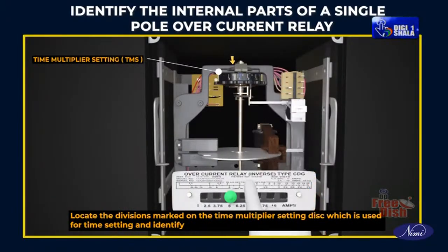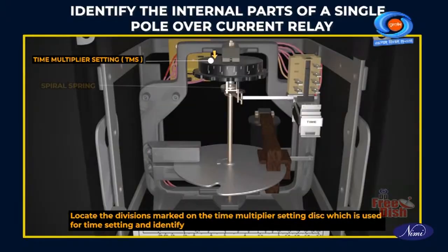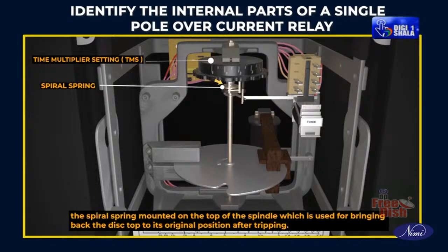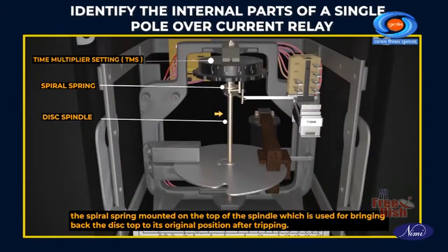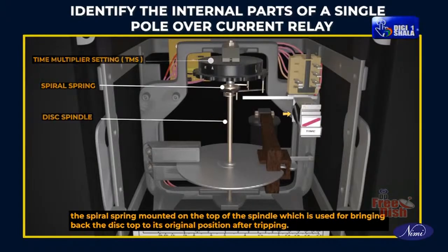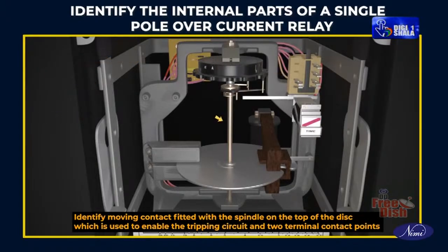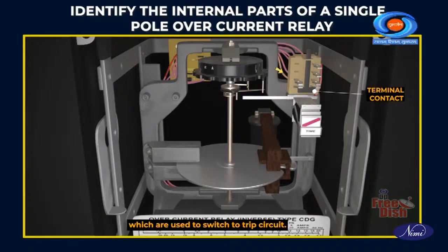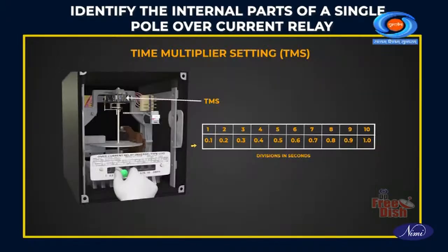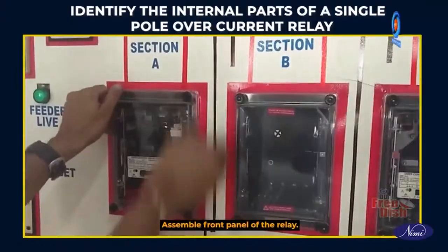Locate the divisions marked on the time multiplier setting disc, which is used for time setting, and identify the spiral spring mounted on the top of the spindle, which is used for bringing the disc back to its original position after tripping. Identify the moving contact fitted with the spindle on the top of the disc, which is used to enable the tripping circuit, and the 2 terminal contact points which are used to switch the trip circuit. Record the readings. Assemble the front panel of the relay.